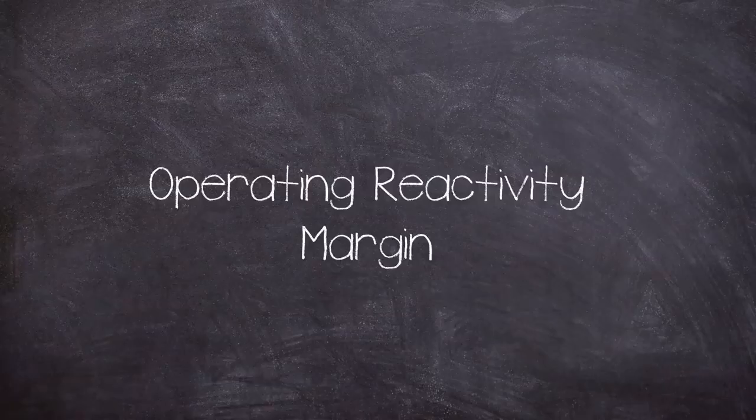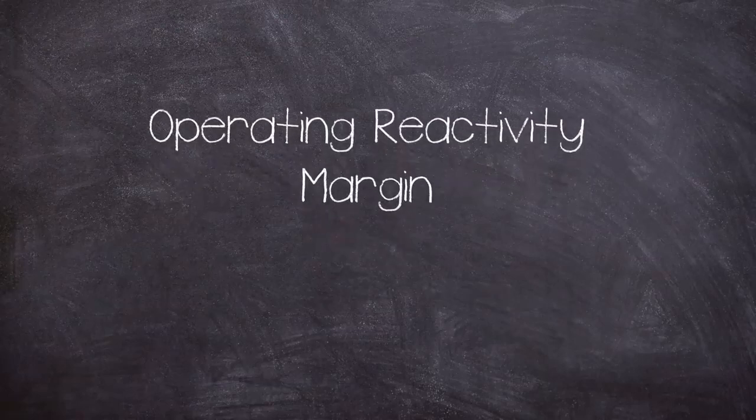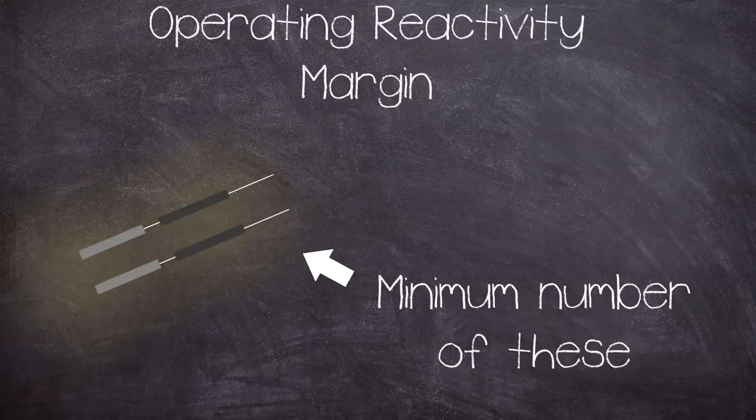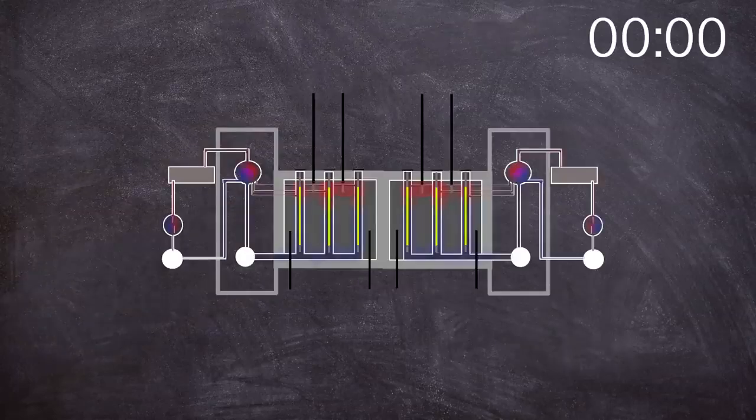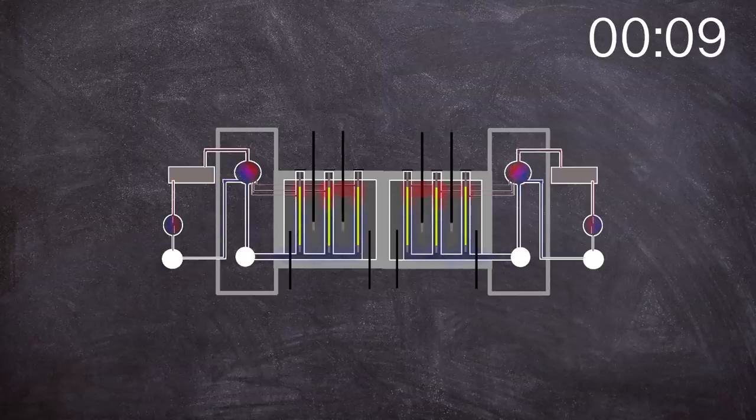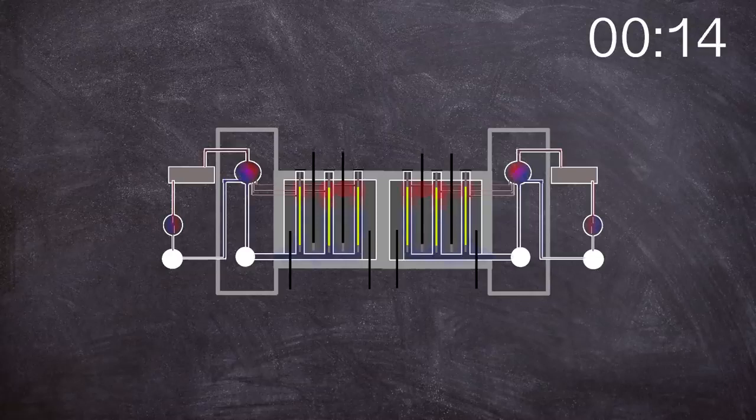Part of this mitigation was having an operating reactivity margin. The ORM is the number of equivalent control rods of nominal worth remaining in the core. Total time required for a scram or insertion of emergency control rods into the core when starting from the upper limit stop switches was around 18 seconds, which was relatively slow due to the size of control rod channels and coolant having to be pushed out of the way. The scram could be initiated by the control system or manually via the AZ-5 button.